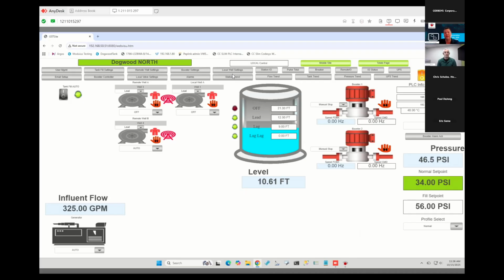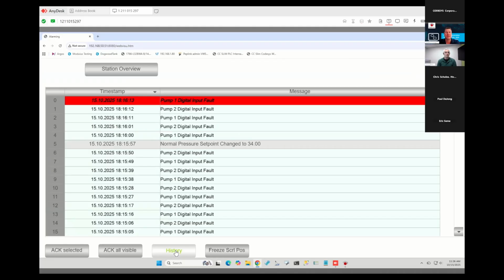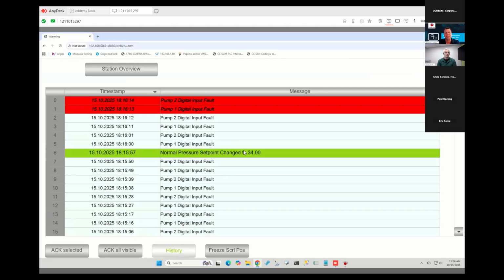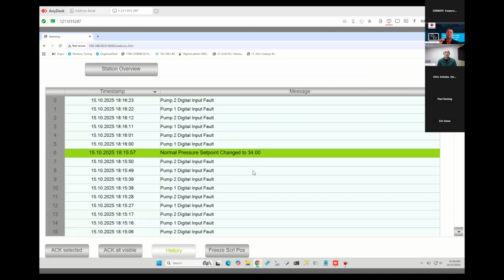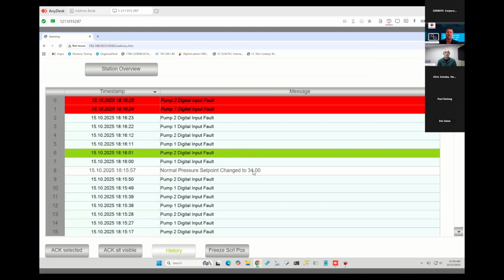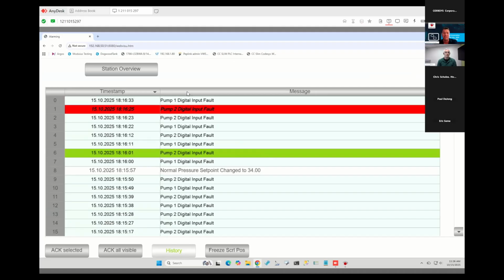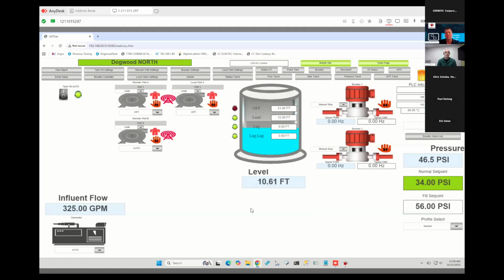So once I do something like that and change it, I'll go back here to my alarms and come to history. And you can see right there, normal pressure set point changed to 34. So we're also tracking what's going on. If they're starting, if they're stopping, if they're changing the hand-off-auto. You can see all the faults we're having right now because the PLC is trying to communicate with that Modbus drive that's not available out there. So all the tracking is built in, and all that's local. And that's a big point here, is they do not need anything else. We're also sending emails out on alarms from the system. So any of those alarms, they can get an email or a text message.